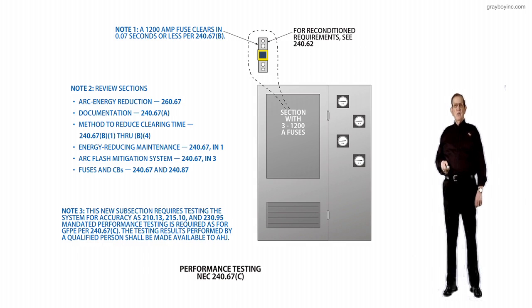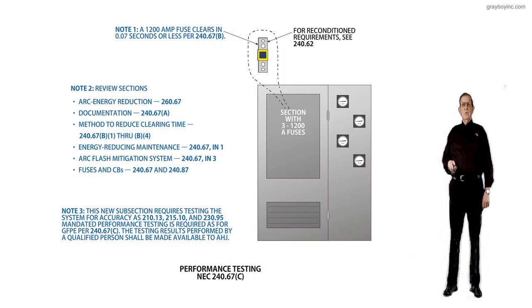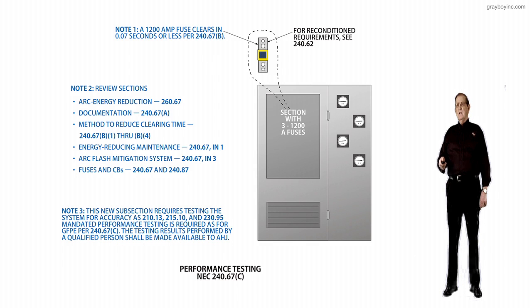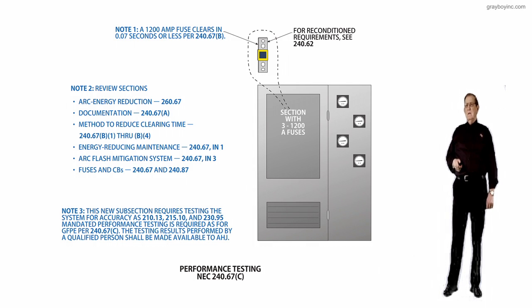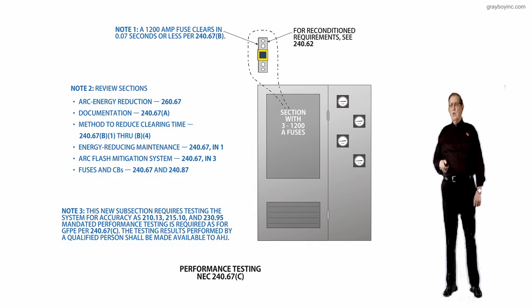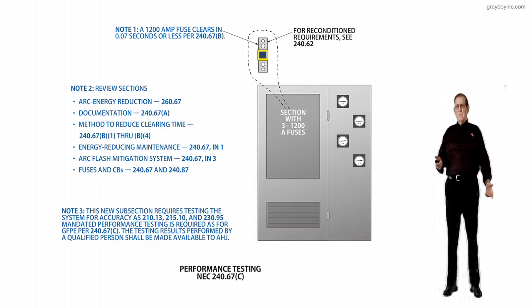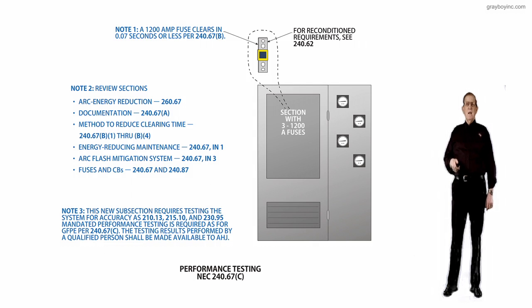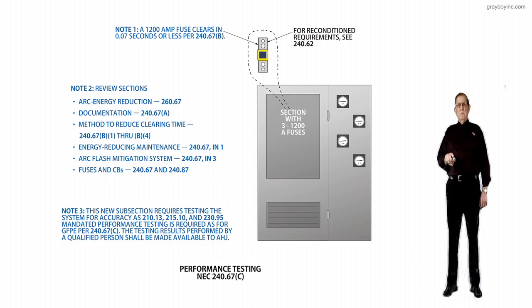The inclusion of performance testing criteria is not new in the National Electrical Code. Sections 210.13, 215.10, and 230.95 have these rules: 210.13 is for a branch circuit looking at ground fault protection of equipment, 215.10 is the same for feeders, and 230.95 is for services. So picking up here, it mandates performance testing of required ground fault protection of equipment, GFPE, when first installed.